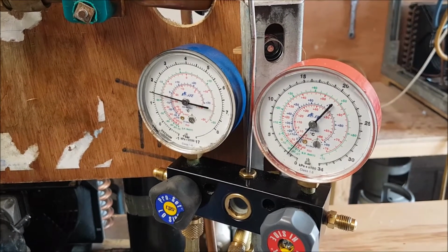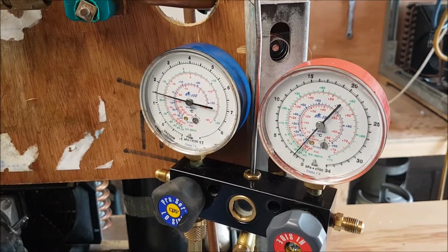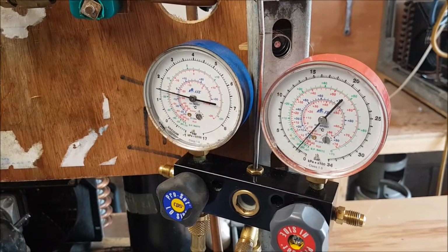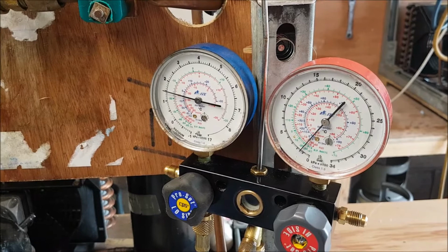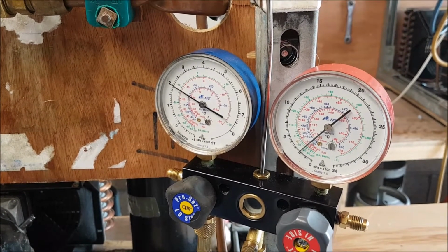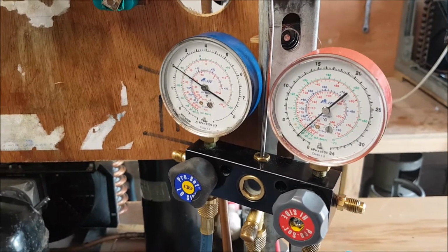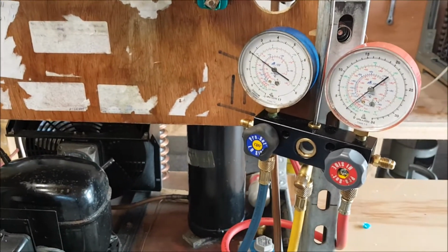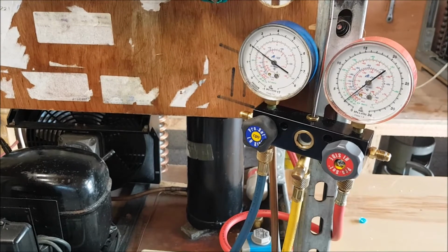And the reason why I'm watching the needles, if there's a big leak in the system, those needles will go back to zero fairly quickly. So I don't want to waste a load of nitrogen. If I was lashing in a load of nitrogen like this into the system, you would find yourself in a scenario where it would be going out as quick as it's going in, and you'd use a bottle before you know it. I got as far as 2 bar there.